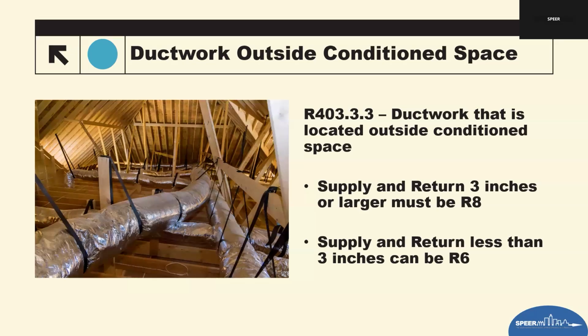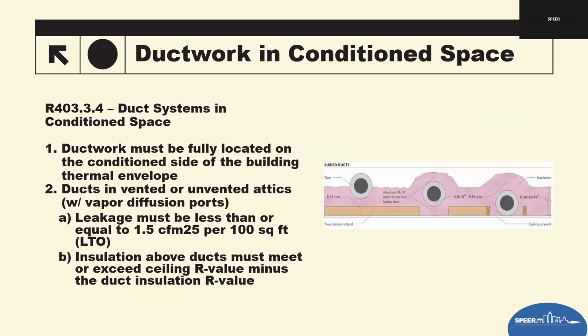That also is in the prior code cycles. It could be one thing in a crawl space and another in an attic. Now, as long as it's outside of a conditioned space, it has all the same requirements. We won't go too much into this, but there are some things to bring up because there is a significant change in what people are calling ducts in conditioned space. This is a picture of buried ducts, but if we say that there's a duct in conditioned space because it's inside of a foam encapsulated attic, the 2024 IECC now clarifies what that means.